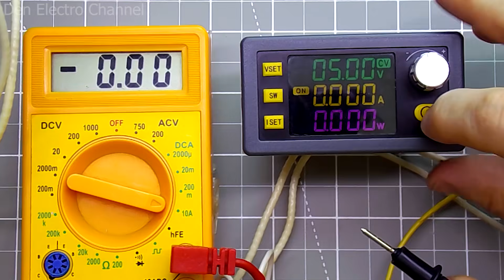Now I'll try it with the wires shorted. I open the output, and the current is slightly higher than set, almost 9.4 amps, but then it drops to 9.1 amps. I close and open the output again. The current immediately returned to 9.1 amps as set.